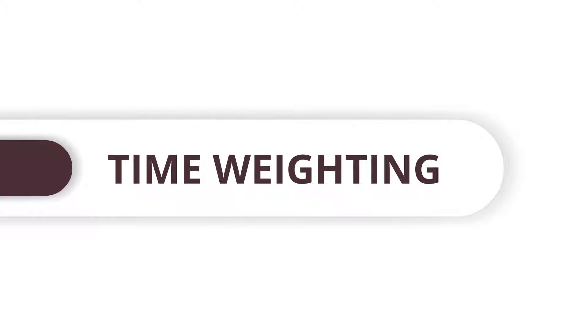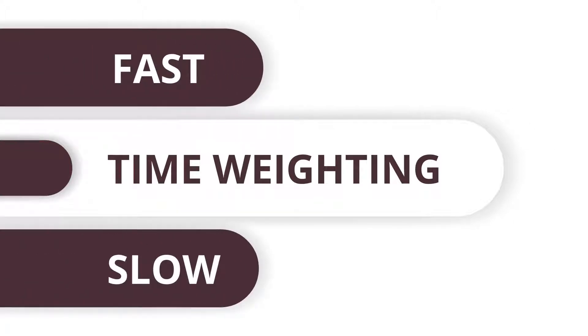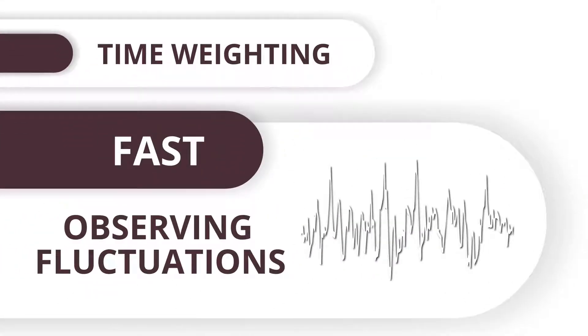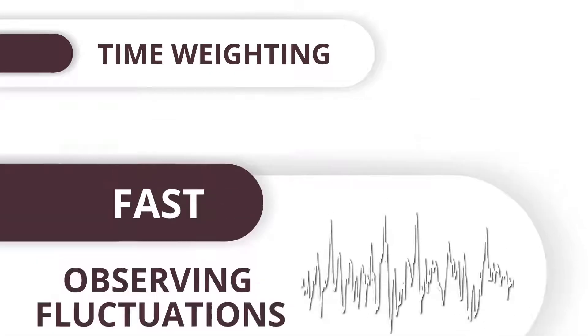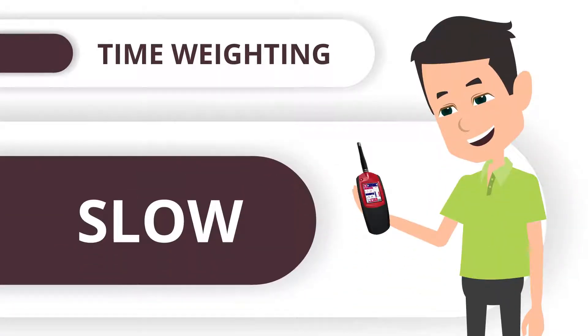Another parameter to be chosen is time weighting. The most common choices are fast and slow, which mean exactly what you would think. The fast time weighting is better for observing fluctuations, whereas the meter may be easier to read when set to slow.